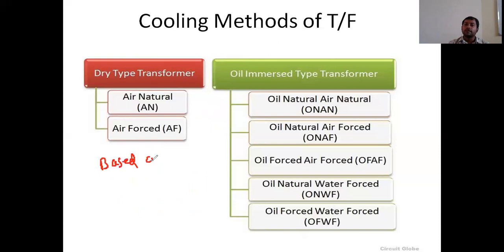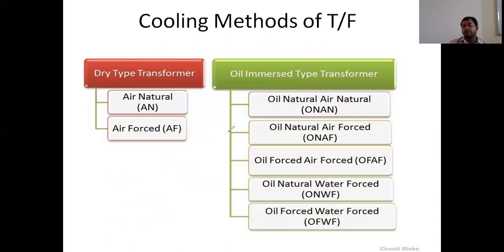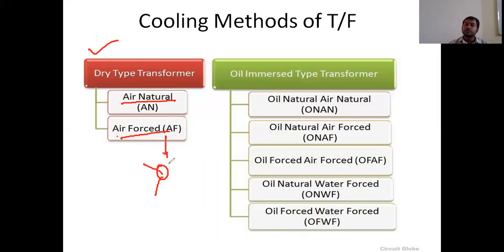Based on the capacity of the transformer — that is, KVA or MVA (kilo volt amps or mega volt amps) — two types of cooling methods are used. One is the dry type transformer cooling system. In this dry type, one method is air natural, where natural air reduces the temperature of the transformer. Another method is air forced, where we need to use separate fans to produce forcible air and reduce the temperature.